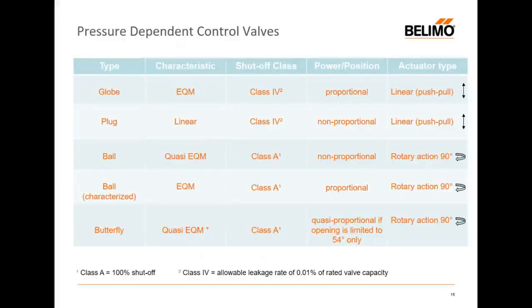So I just want to touch now on the pressure dependent types of trim, the type of valve that you might choose. Commonly in our market, there are probably two or three types. The globe valve is the most common, simply because it inherently has an EQM characteristic. It's got a class 4 shutoff. I'll go back to that in a second, but it does give us that proportionality that we're looking for. And it's actuated by a push-pull actuator, pushing against the spring and pulling the valve open and closed.